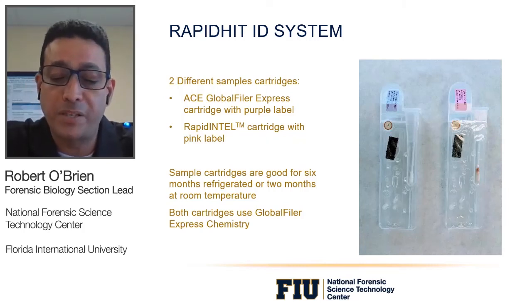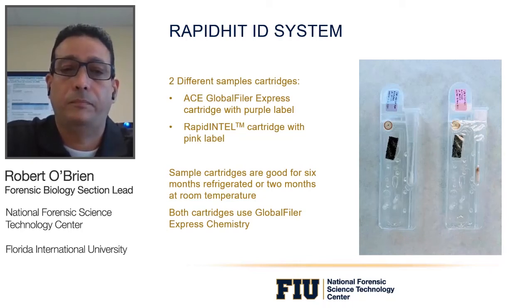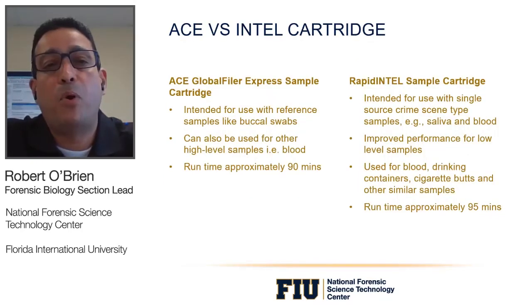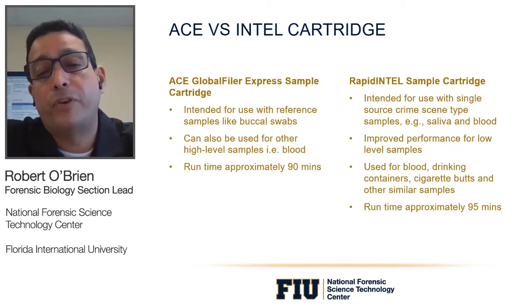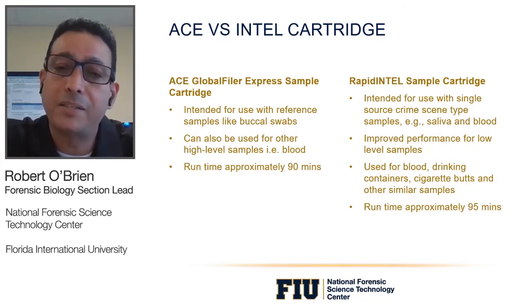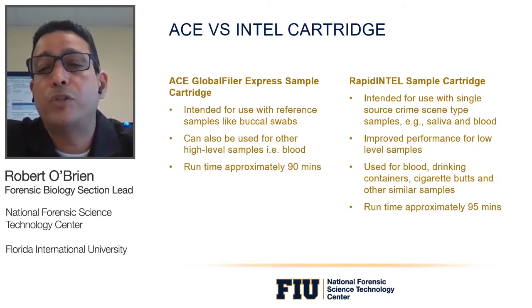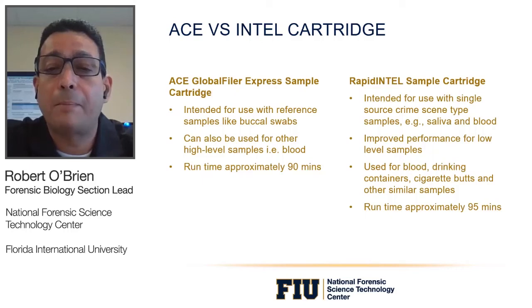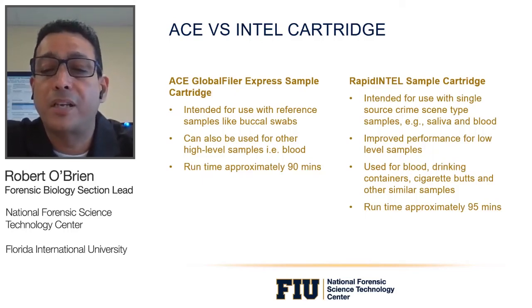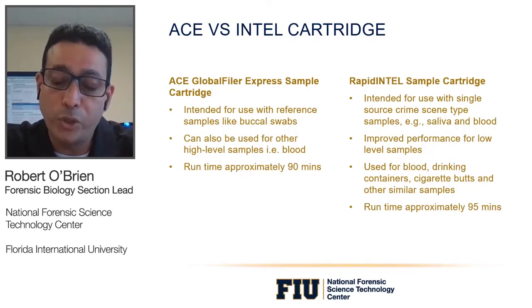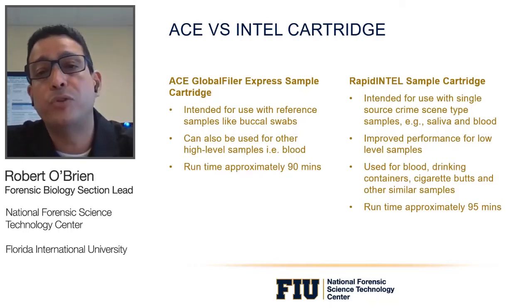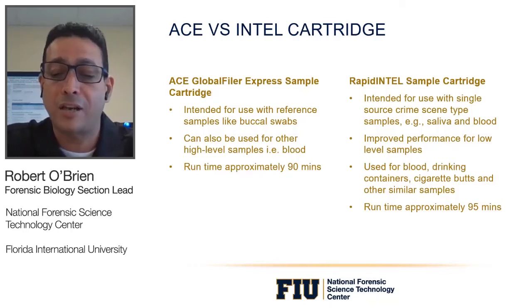There are two different sample cartridges: the ACE Global Filer Express cartridge (purple label) intended for reference samples like buccal swabs and high-level samples like blood, with a runtime of approximately 90 minutes; and the Rapid Intel cartridge (pink label) intended for single-source crime scene samples such as saliva and blood, with improved performance for low-level samples and a runtime of approximately 95 minutes. Both cartridges can be stored up to six months refrigerated or two months at room temperature, and both use Global Filer Express chemistry. The instrument automatically determines the correct runtime based on which cartridge is inserted.